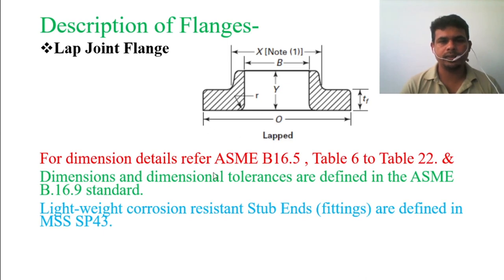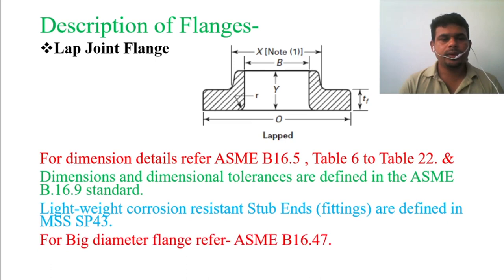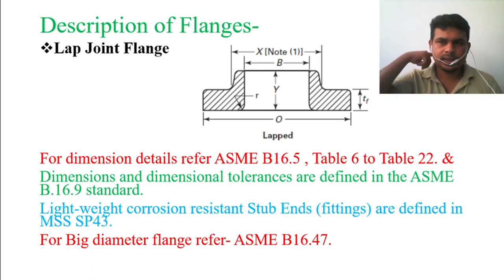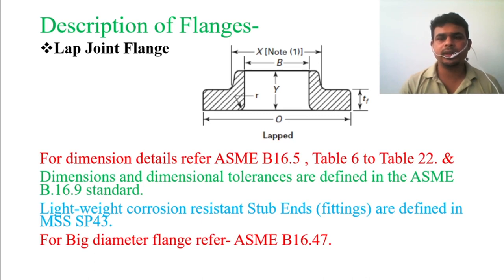If you go through these standards, you will be able to understand all the dimensional tolerances in detail. My lectures aim to give you basic information and key references — if you are more interested, you can visit these standards to learn more. For big diameter flanges, refer to ASME B16.47. As I mentioned in a previous lecture, ASME B16.5 covers up to 24-inch flanges, and from 26 to 60 inches you need to refer to ASME B16.47.